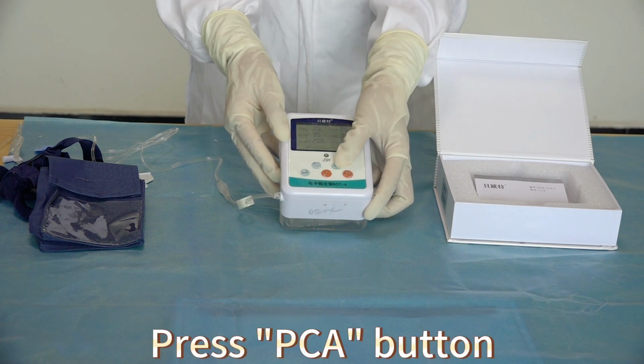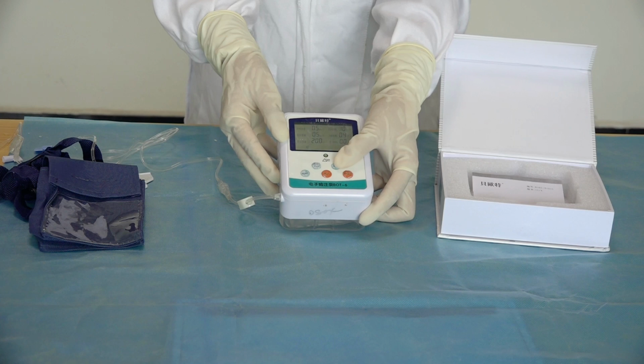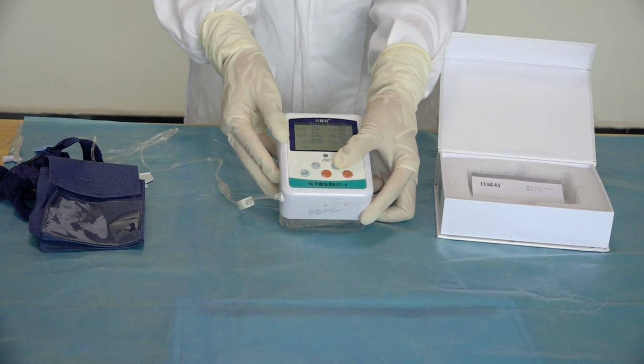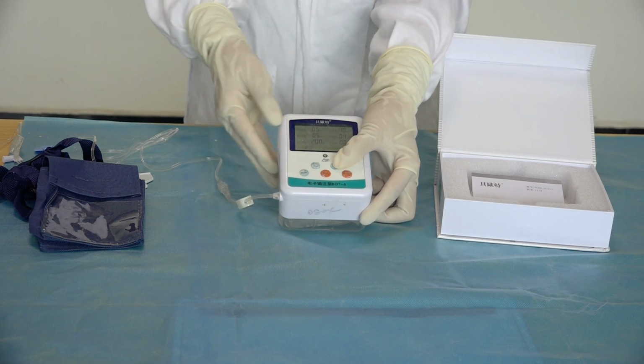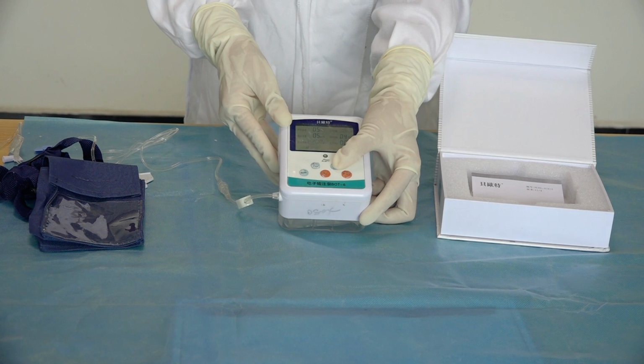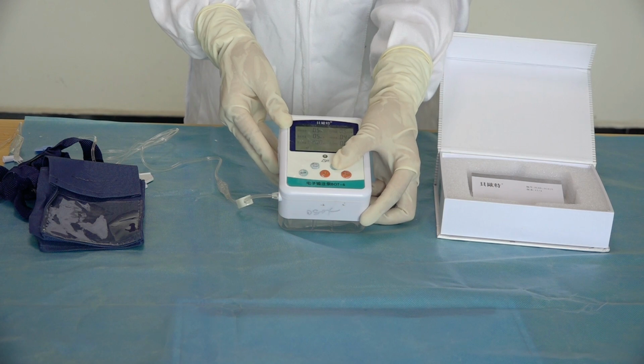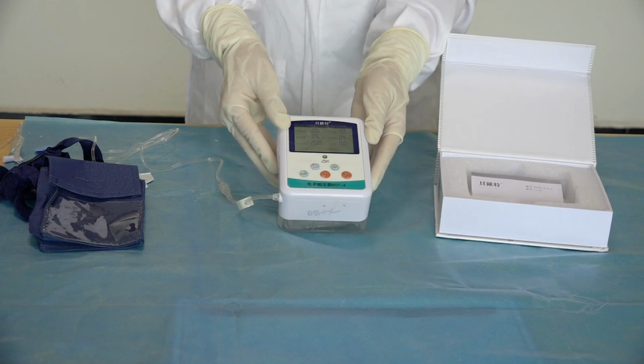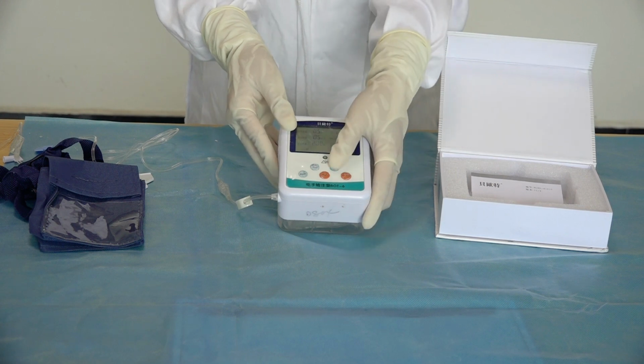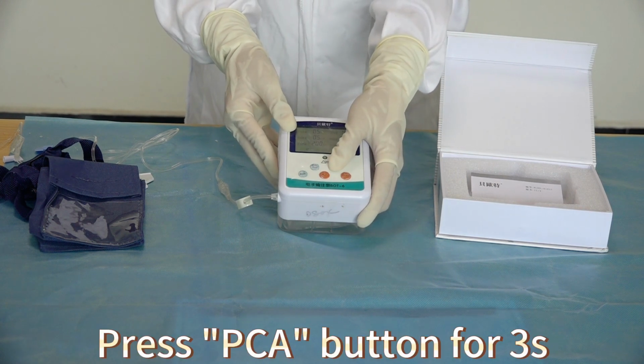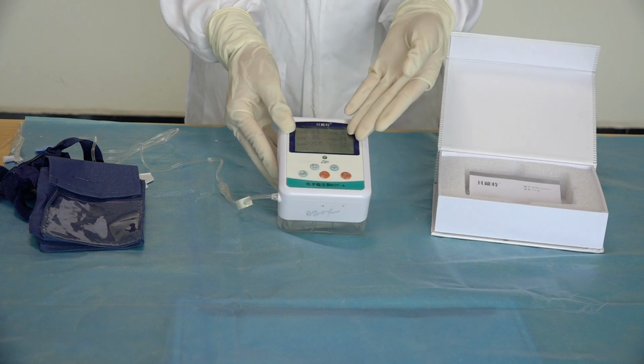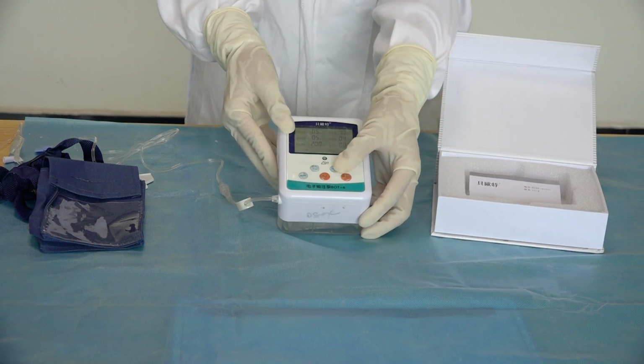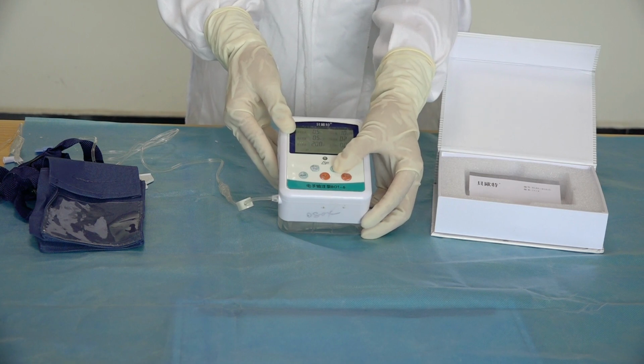Press the PCA button to set the PCA volume within the range of 0.5 to 9.9 ml per time. Press this button once to increase the PCA volume by 0.5 ml per time, but an increase of 0.4 ml per time from 9.5 ml per time to 9.9 ml per time. Press the PCA button for 3 seconds, and the electronic infusion pump emits a bleep sound D, which can set the PCA times within the range of 1 to 20 times per hour.